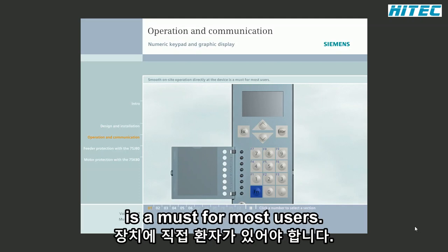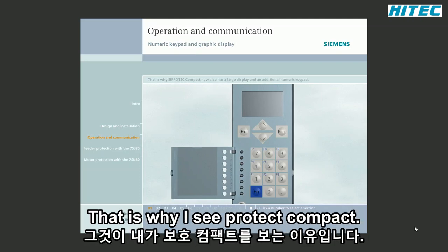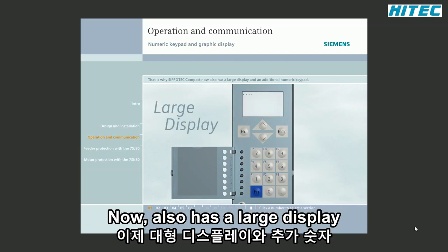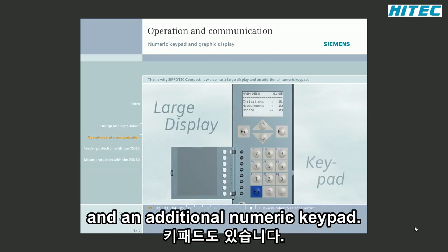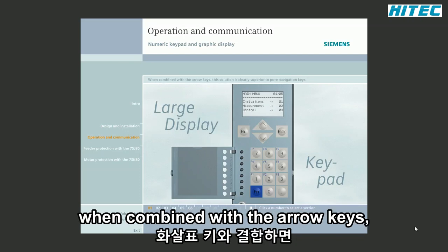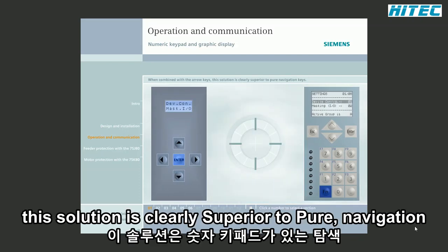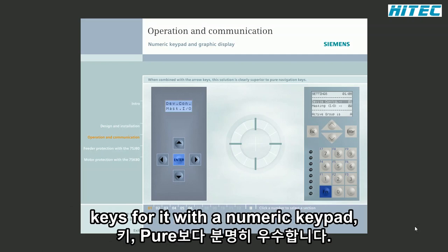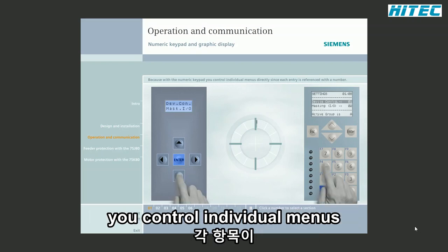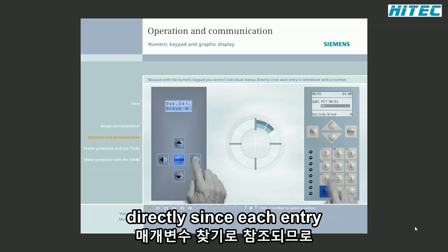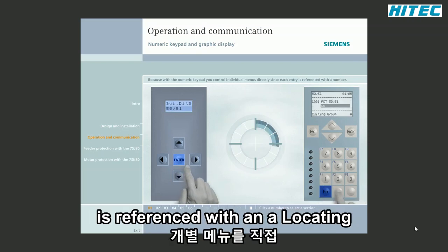Smooth on-site operation directly at the device is a must for most users. That is why SIPROTEC Compact now also has a large display and an additional numeric keypad. When combined with the arrow keys, this solution is clearly superior to pure navigation keys. For with a numeric keypad, you control individual menus directly, since each entry is referenced with a number. That way, you're already one ahead of the rest when locating a parameter.